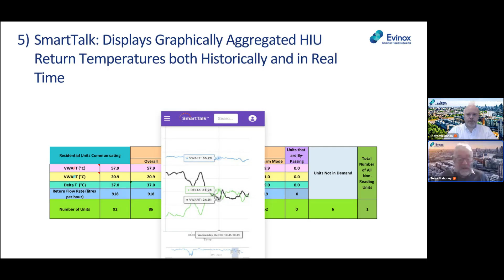Or in this case, we're looking at taking positive action to reduce the overall return temperature based on HIU data, which we can see in real time. This confirms that the action we were taking at that point in time contributed positively to the performance of the heat network by reducing the overall return temperature.